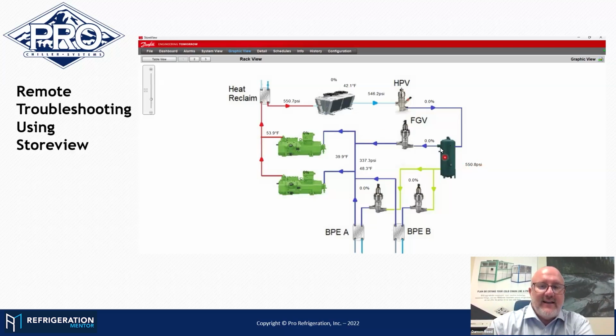I can see it's 580. I know that, 550. I know that that's my control. I expect my flash gas valve to be at 0%, which it is. My high pressure valve's at 0% as well. My evaporators are off. So, this is suction superheat here, and suction pressure, suction temperature, discharge temperature, and then there's a little 0% above each compressor. It's just saying, hey, I've got 0% compressor capacity.